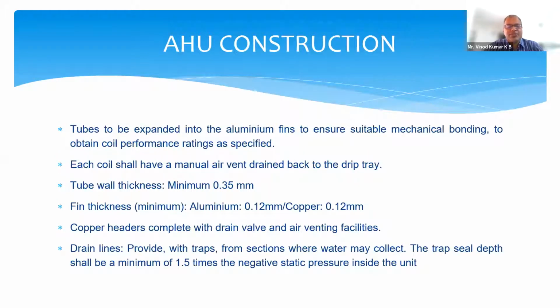Here again, this specification talks about the thickness of the tube as well as the fin thickness, which is important for the selection, so you get the right kind of copper tube inside your coil. And as the water condensation happens in the coil, you should have a proper drain pan, and the drain pan will be connected to the drain pipe.